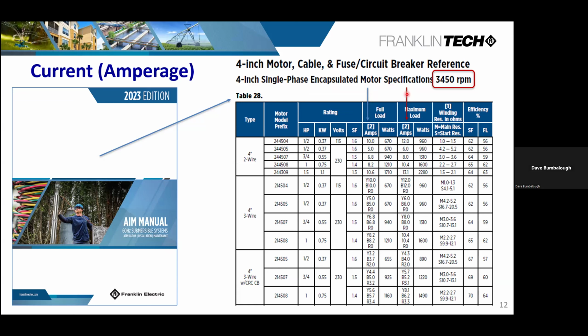And then they list a max load, which takes into consideration a service factor, which only affects the horsepower. So, for example, a 1 horsepower motor, as we're looking at here, has a service factor of 1.4. That means that 1 horsepower motor is equivalent to 1.4 horsepower. If you were running it into that 1.4 horsepower, you're going to pull 10.4 amps as its maximum. If you're running it lower, around the 1 horsepower range of that motor, then you're going to pull 8.2 amps.